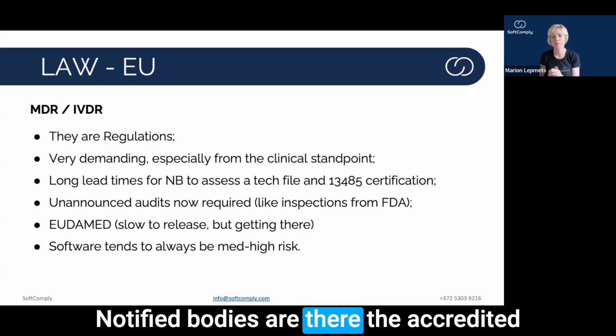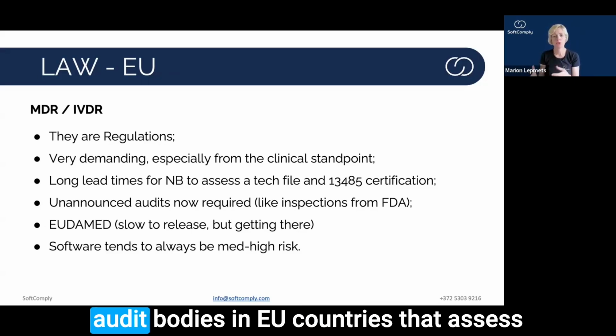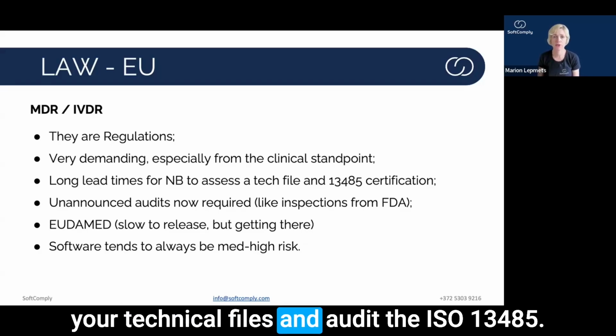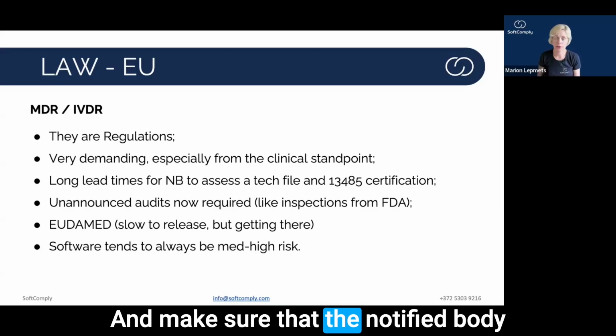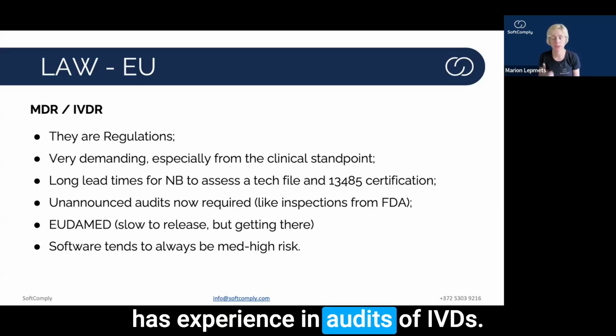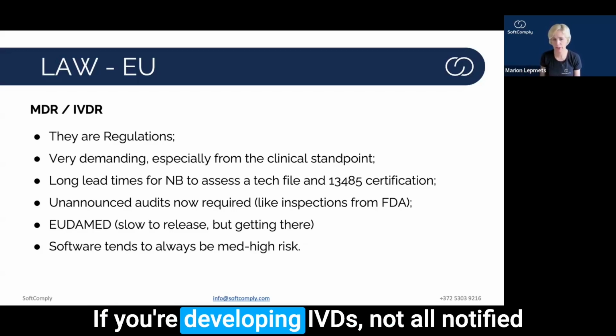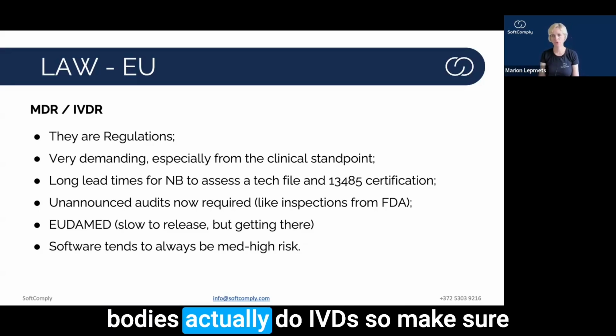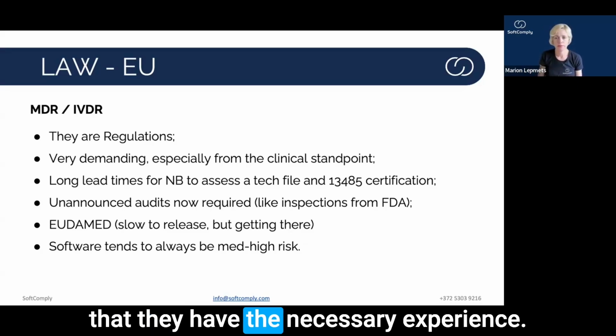Notified bodies are the different audit bodies in EU countries that assess your technical files and audit the 13485. And make sure that the notified body has experience auditing IVDs. If you're developing IVDs, not all notified bodies actually do IVDs. So make sure that they have the necessary experience.